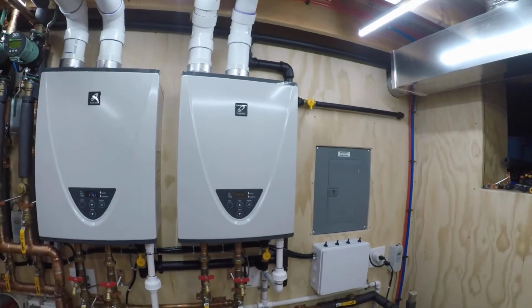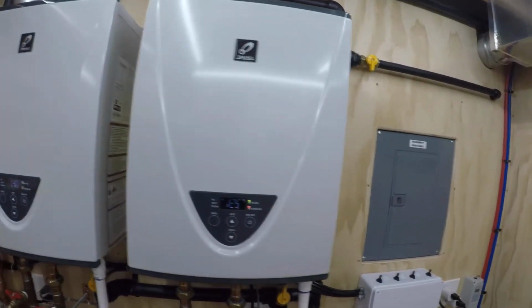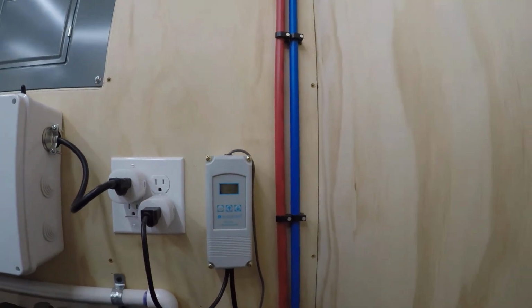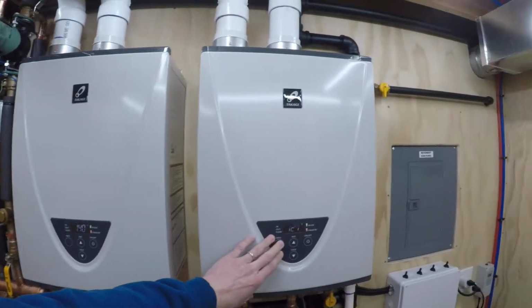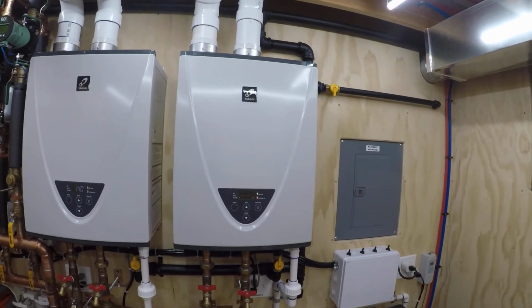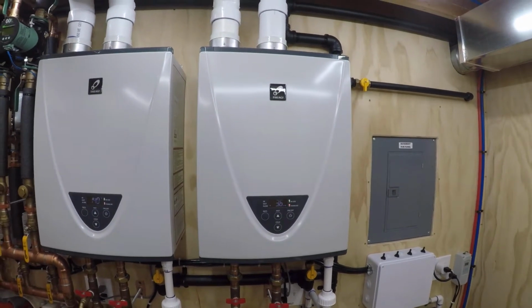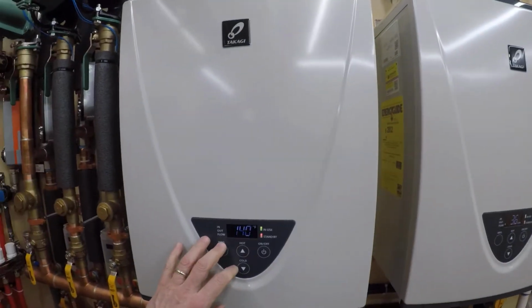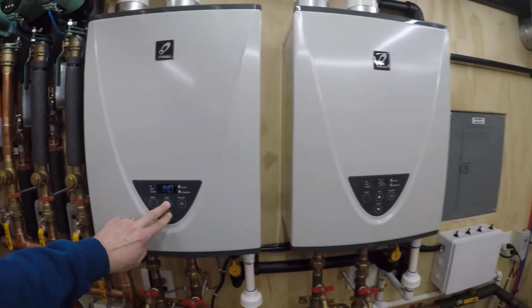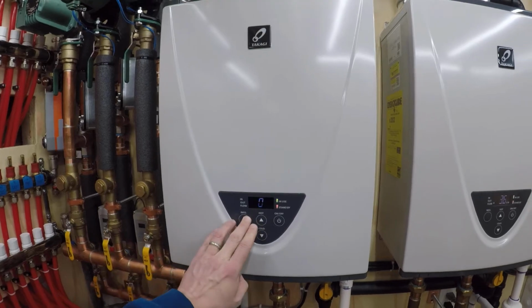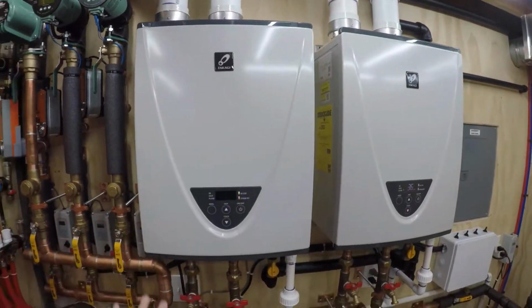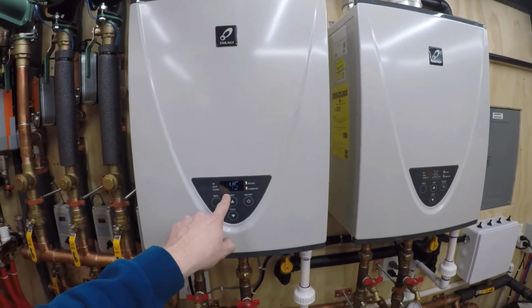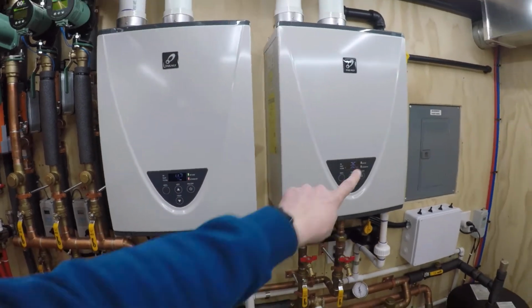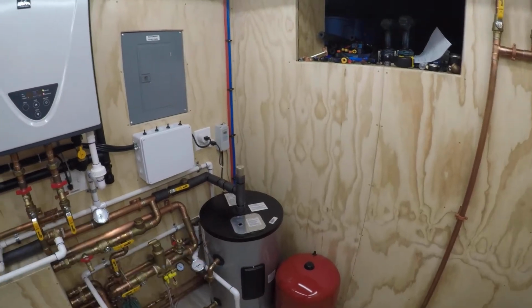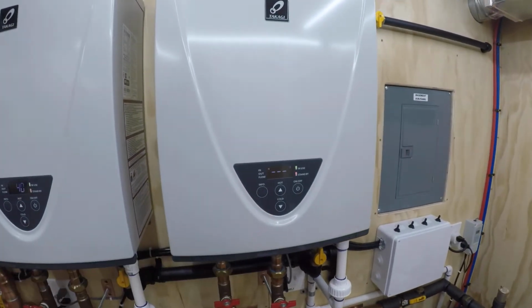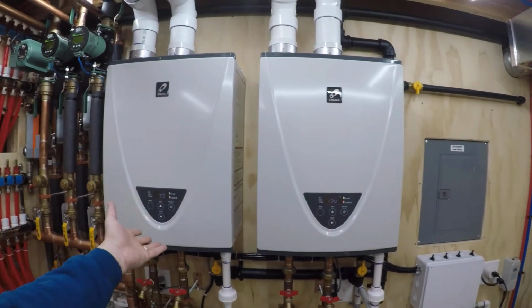And you can see here that right now we've got 125 degrees coming in. The tank's reading about 123 degrees. And we've got 140 degrees going out. And we're flowing about, it should be about 3.8, 3.9, okay, 3.6 gallons a minute through each heater. We can also put this unit into diagnostic mode here, and I can tell you what the total BTU draw is for the whole system amongst both units. So right now we're using about 45,000 BTUs, so about 22.5 per unit, to bring the water in that tank from 120, probably 128 by now, 127, 130 to 140.